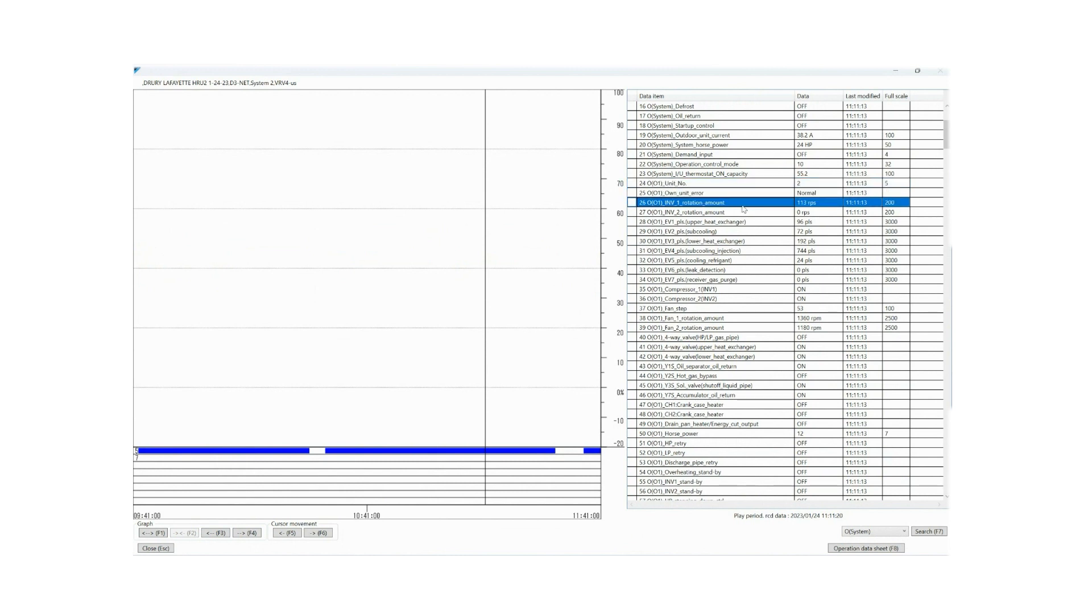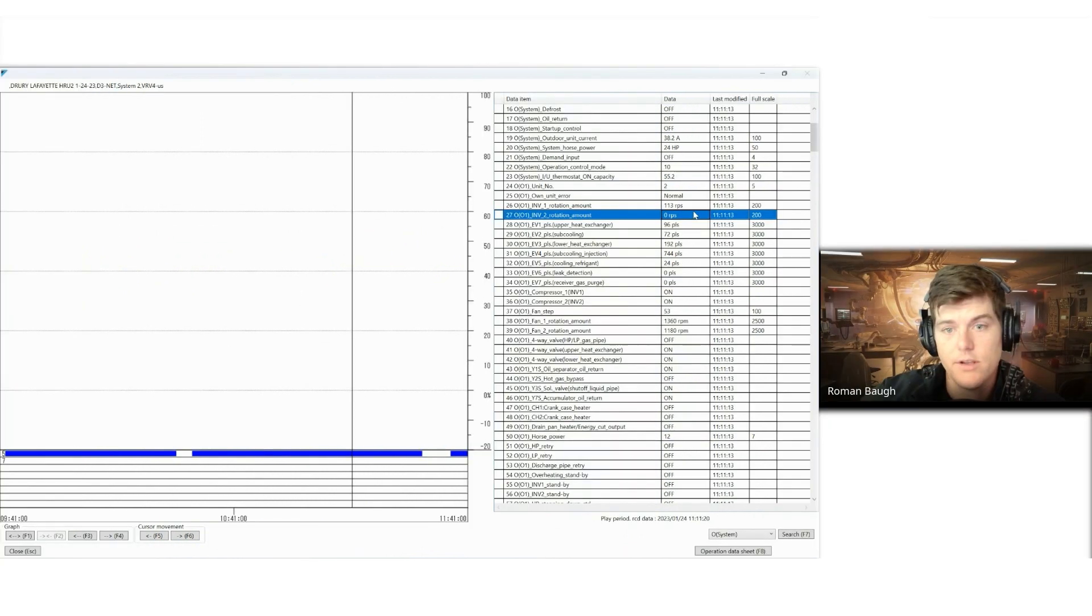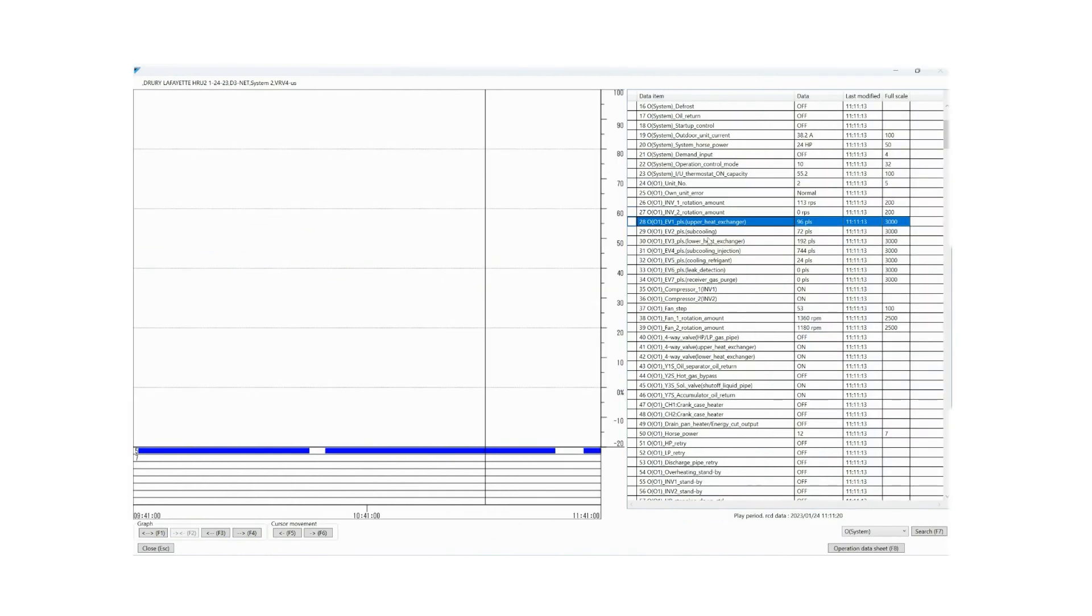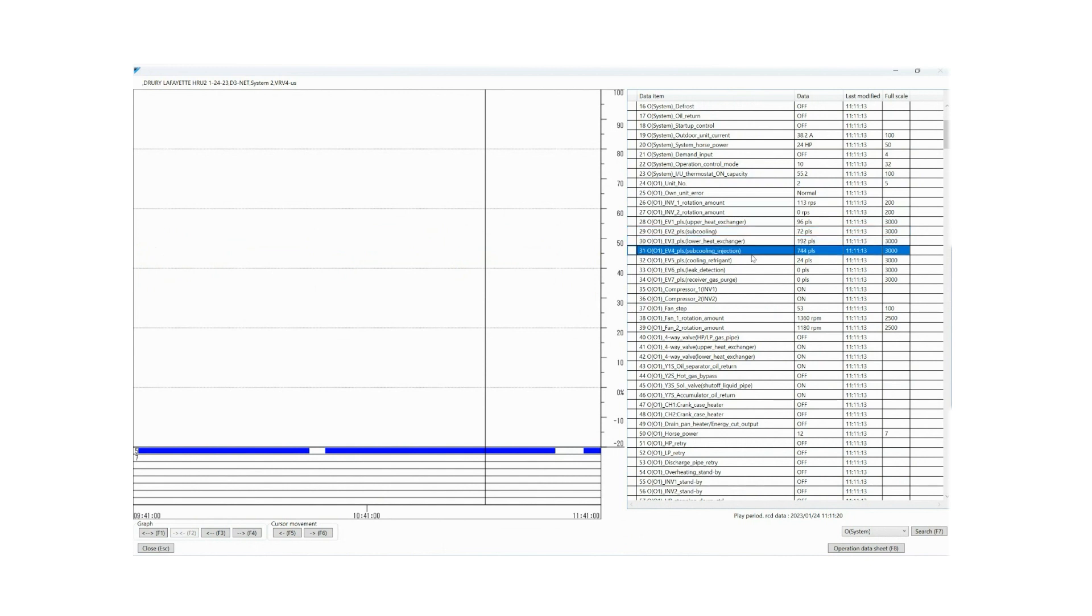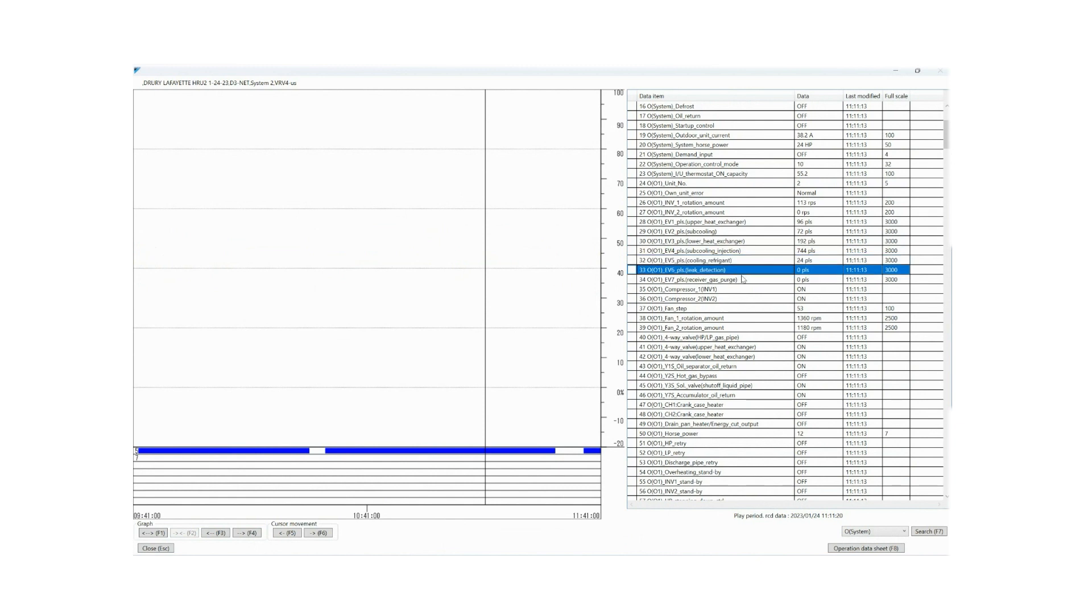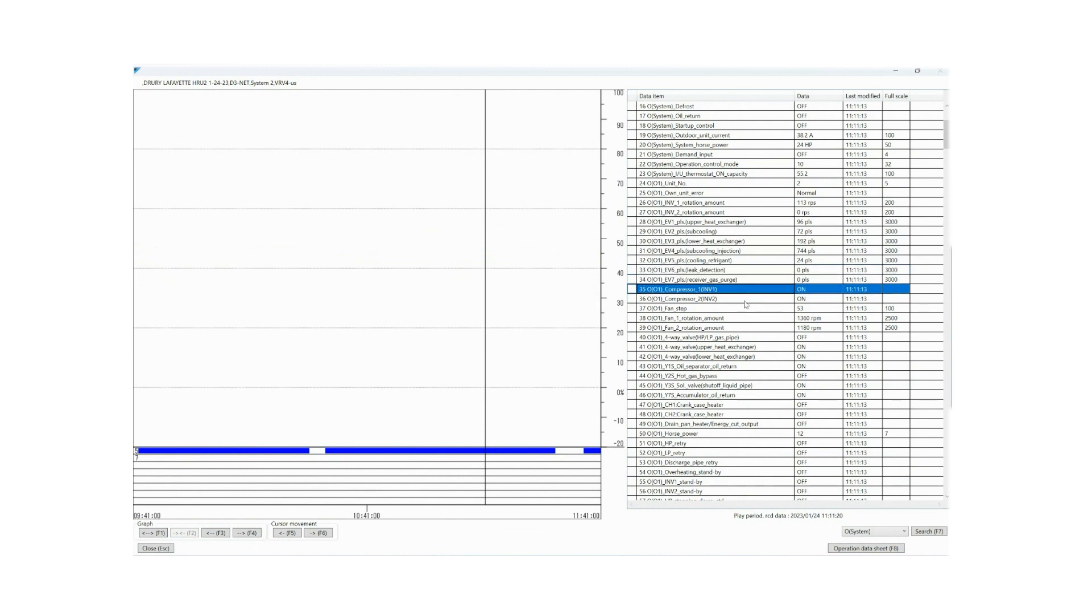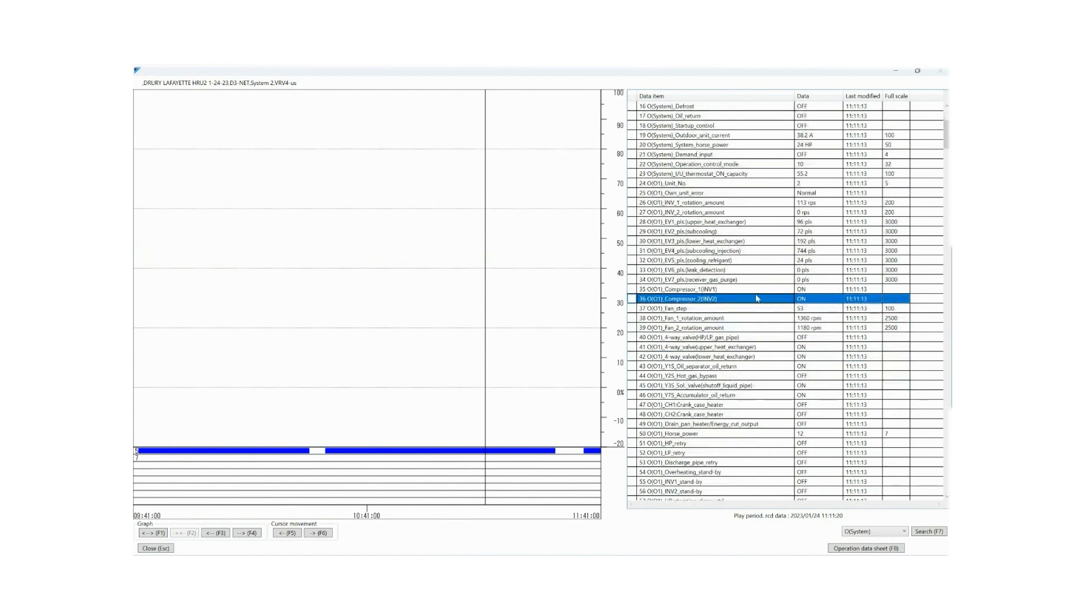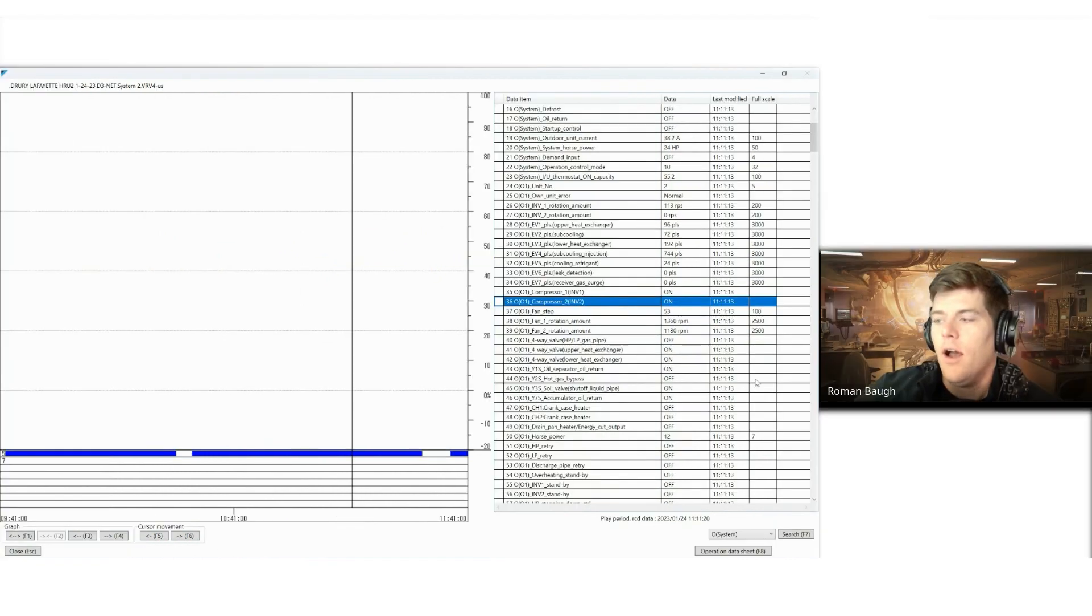So you'll notice that I have my unit number. This is just your D-III net address, for your outdoor unit. Is it an error? No, it is not. Revolution of my first compressor. Does it have a second compressor? If it does, here is where the revolutions would live. Expansion valve upper heat exchanger, subcooling expansion valve lower heat exchanger, subcooling injection. This tells me if it has a subcooling injection that it's most likely a VRVX system or it could be an Aurora. Cooling refrigerant circuit. This is your loop across your inverter board. Leak detection. You don't use this valve in our market, so you can ignore it. Receiver gas purge. That's on your accumulator. And we've got our compressor, whether it's on or off. The control board system is telling us yes, this compressor is on. Inverter 2 is on, even though it may not be. Don't think that that's a programming error. That's just the way that they set up this system to read out data points.